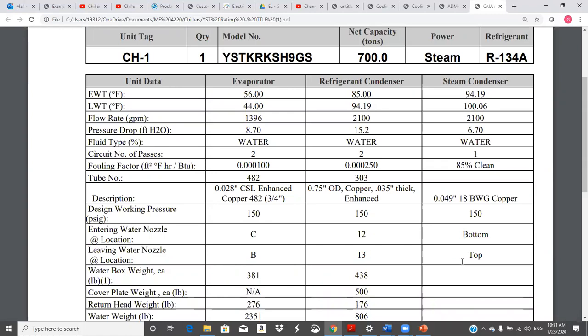Look, we're going to size this tower for 100 degrees in. We got 94 out here. We got 94 in here. We got 85. So you see, we're taking this same condenser water flow through the condenser here first and the steam condenser second, because this is the cold water out of the tower. Pressure drop, feet of water: evaporator, condenser, steam condenser, fluid, water, circuit passes, fouling factor. Get you back to your heat transfer days.